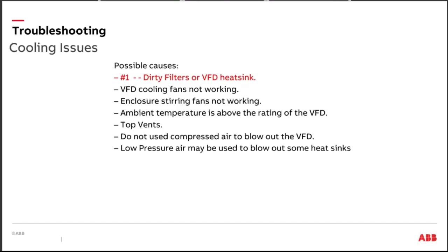Okay. Now, when I look at filter kits, one of the things, if you're the person that's going to be specifying, you want to make sure that your filters are on the outside of the drive enclosure. You do not want to open the door to change the filter. And as crazy as that sounds, there are companies that actually put the filter on the interior side of the door. Okay? That filter should be on the outside for a couple different reasons. But first and foremost, if I leave my door shut, I remove my employee out of the arc flash zone. Okay, that door is shut and bolted closed. Now there's no reason for him to open it to change the filter.